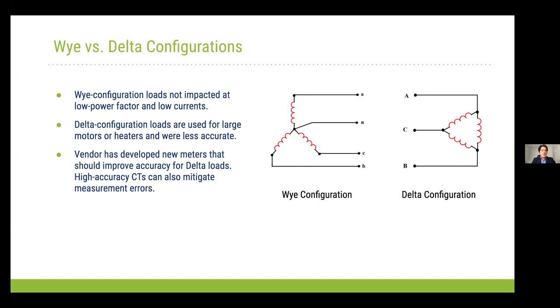For the delta configuration, as I showed you in the graph, that was a slightly different case. We saw that at low power levels, there was some discrepancy there. The vendor has stated that they developed new meters that can improve the accuracy for that type of load. NREL has not validated those meters, but if somebody's interested, they would be able to follow up with the vendor on that. It's also important to use high accuracy CTs that can also mitigate those measurement errors as well. I just want to point that out. I think we can go to the next slide.